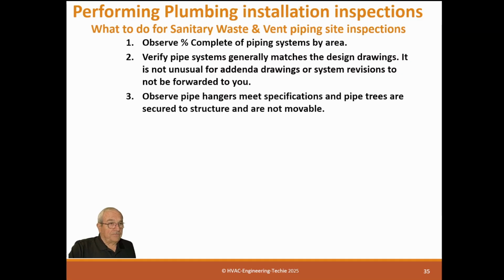That's important. Observe pipe hangers meet specifications, and pipe trees are secured to the structure and are not movable. So what you do is you walk up to a pipe tree and shake it. If it moves, that ain't right. It needs to be secured. So if the wall's not been put up yet, don't do that. But if the wall's up and the pipe's in there, but it's not secured to the wall, you need to shake it. Some people seem to think that the freestanding pipe will just take care of itself, and it won't. It needs to be secured.